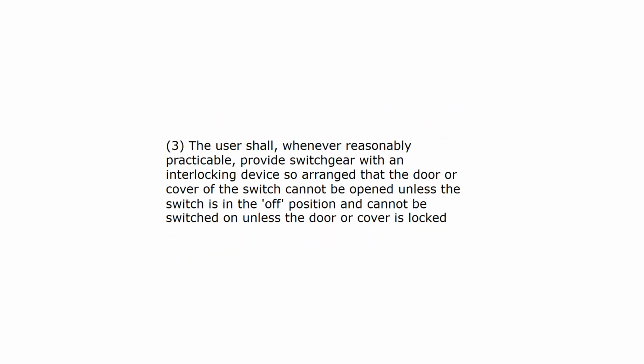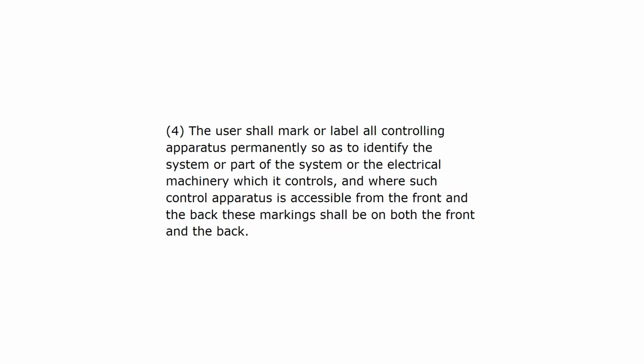The user shall, whenever reasonably practicable, provide switchgear with an interlocking device so arranged that the door or cover of the switch cannot be opened unless the switch is in the off position and cannot be switched on unless the door or cover is locked. The user shall mark or label all controlling apparatus permanently so as to identify the system or part of the system or the electrical machinery which it controls, and where such control apparatus is accessible from the front and the back, these markings shall be on both the front and the back.